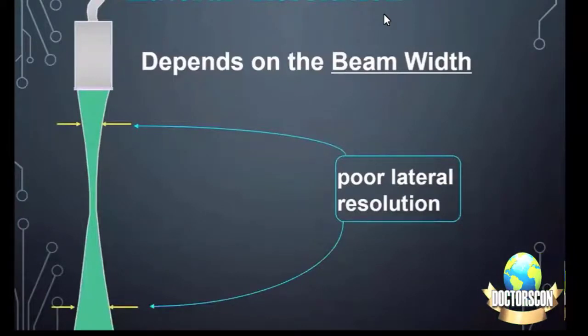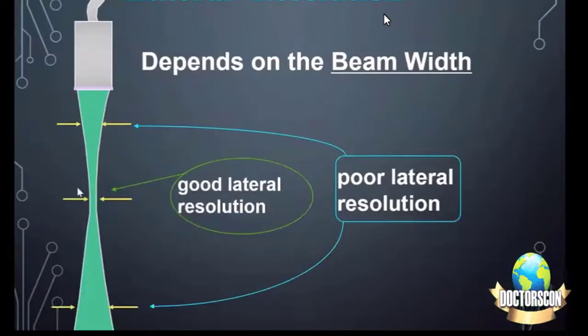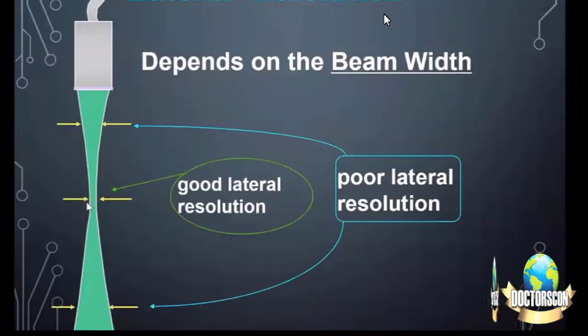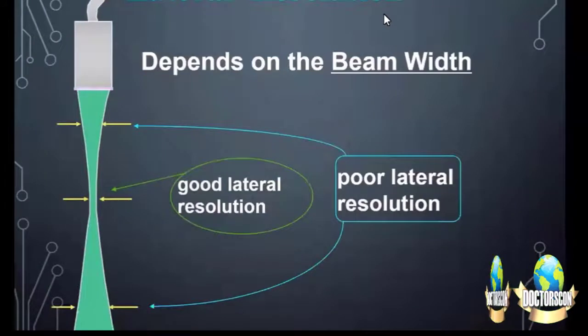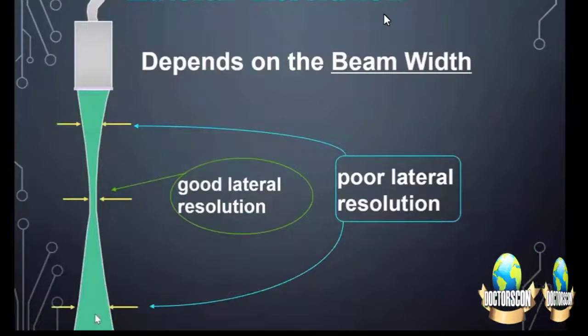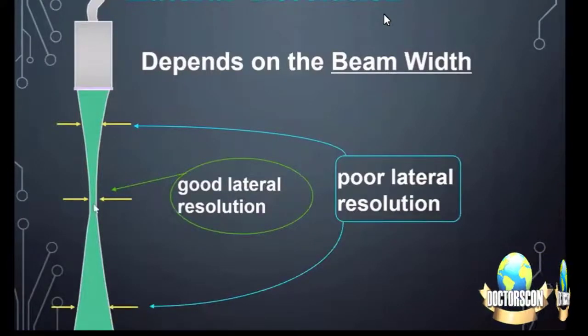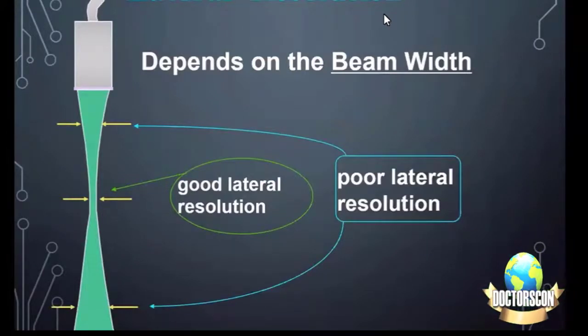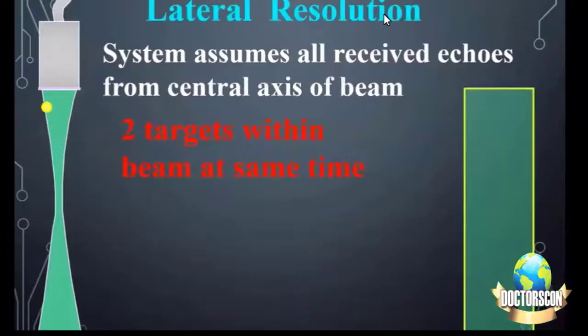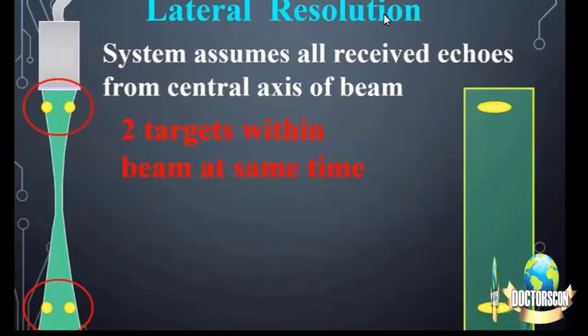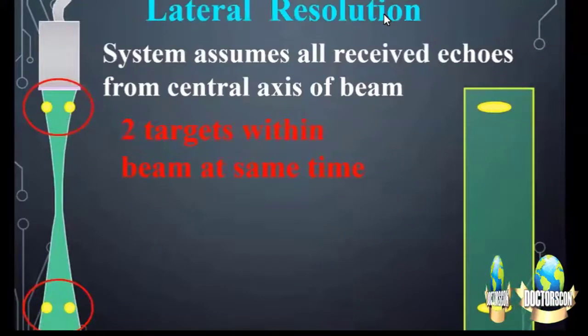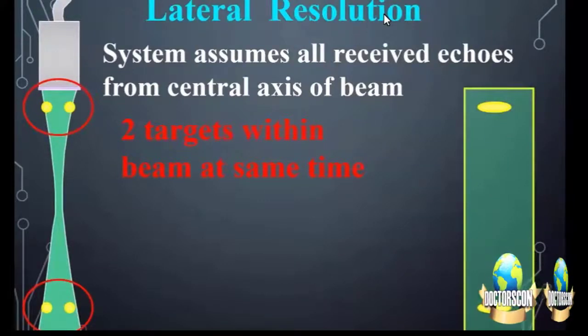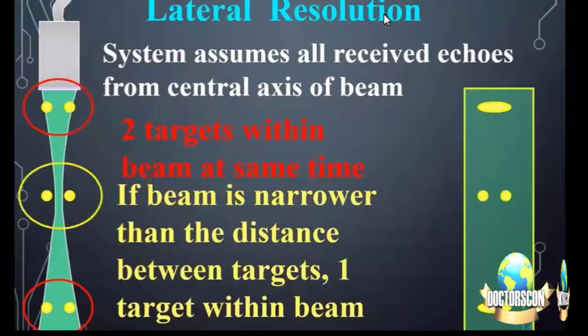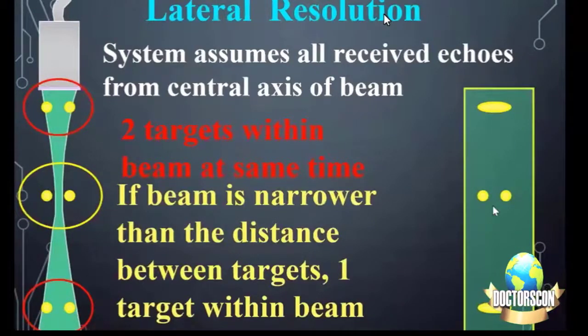Lateral resolution depends upon beam width. So we can adjust the beam width. We try to bring the structure into the center of the beam. Then we will get the best lateral resolution. If we bring it here, both structures will combine and appear as one structure. So the art is to have the structure in the center. We adjust it by decreasing the width of the beam through the knobs. If the structure is here or here, where the width of the beam is more, the structures will appear united, mixed up. And if it is like this, we can see the structures distinguished from each other.